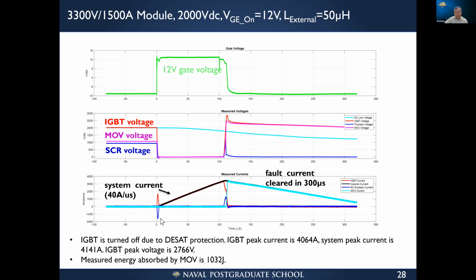Voltage divider. And we turn on the devices, then the current will start to increase because you have fairly large inductance. The current is only rising at 40 amps per microsecond, right? And it will trigger the DESAT protections. Then after a delay time, the IGBT peak current is about 4,000 amps, and the system peak current is about 4,100 amps, right? There's some additional current flowing through the snubber. The SCR is triggered on time and kicks in the MOVs. The peak voltage in this case is about 2766 volts, which is way below the 3.3 kilovolt IGBT voltage rating. After that, the fault is cleared in about 300 microseconds.